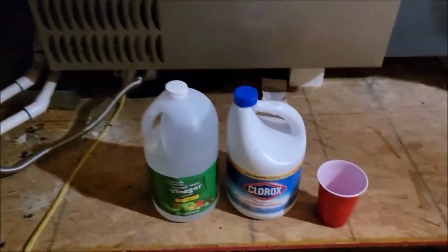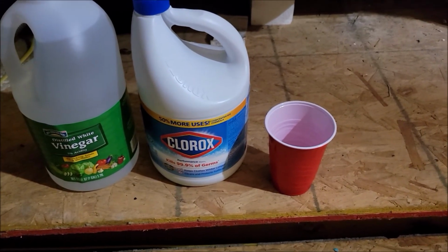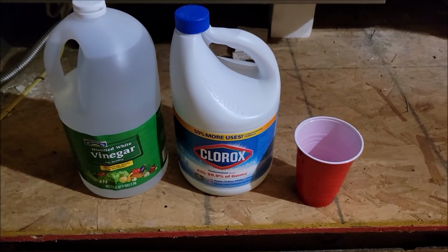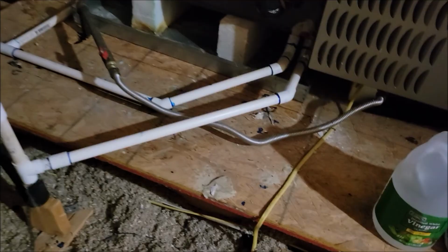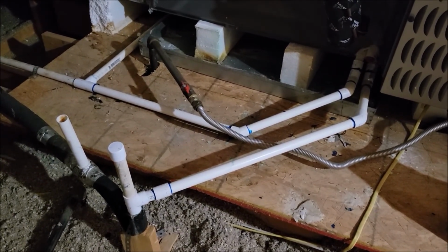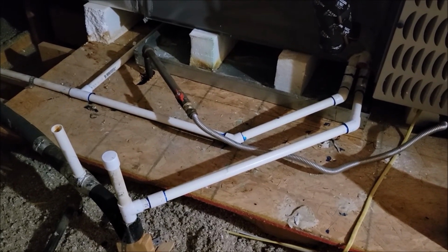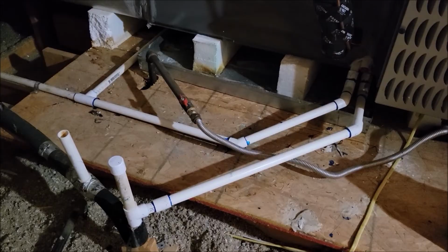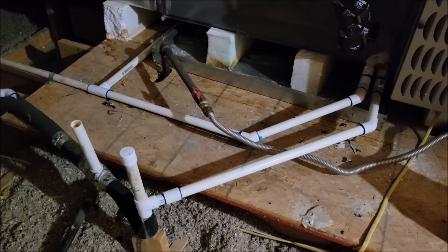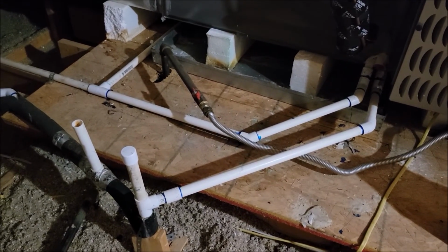Basically, you'll use one of these liquids, whichever you choose. Bring a little cup because you want to do just small amounts at a time. You don't want to just pour it in there. You pour it in very slowly so that none of it works its way back up the drain line. You want it to work its way down the drain line, and you just want to get enough in there, maybe a cup of whatever liquid you choose. You slowly pour it in and let that slowly go down the drain line, coat the lines, and kill whatever's in those lines that are making the buildup.